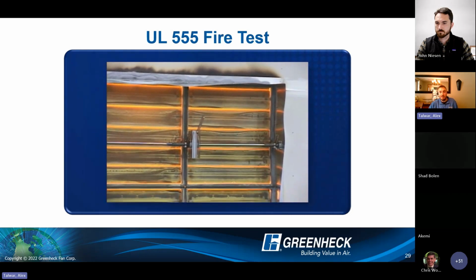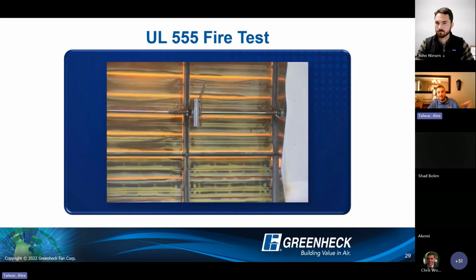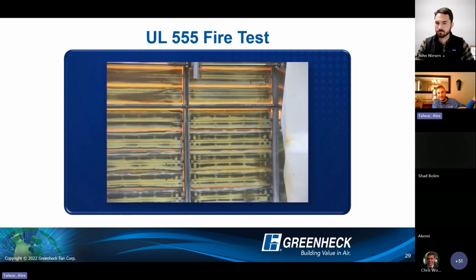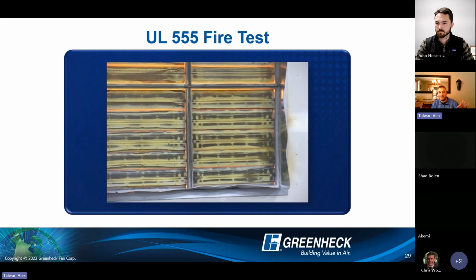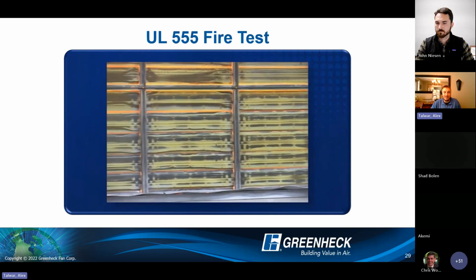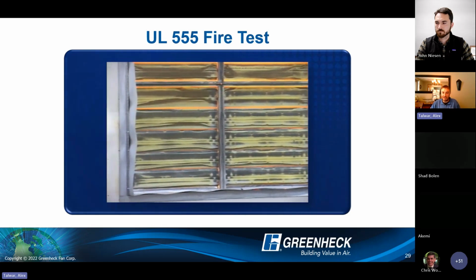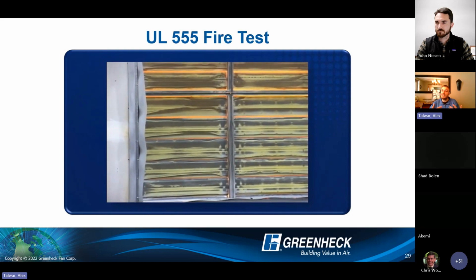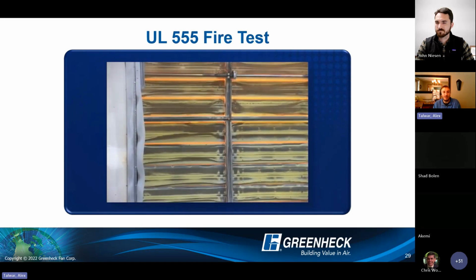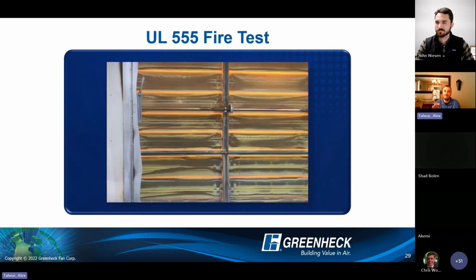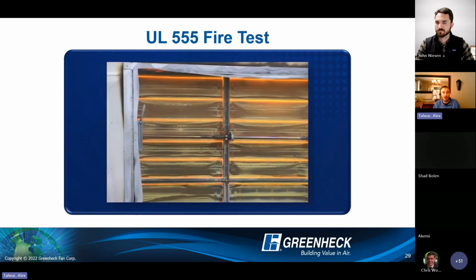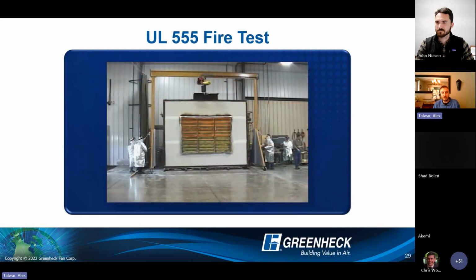So here you can see we're in the middle of the test. It's glowing orange. You can physically see the galvanized zinc material kind of fading away from the blades. Pretty cool test to witness. Doesn't smell great, but during the test, there's not a whole lot you can do except for watch it. If you do see any flame make its way through, it's an automatic fail. So we're always looking for that.